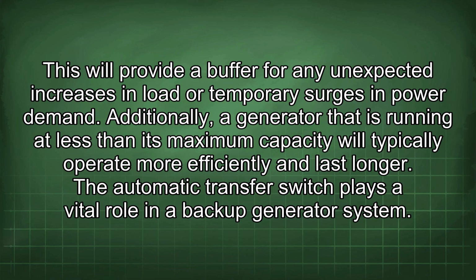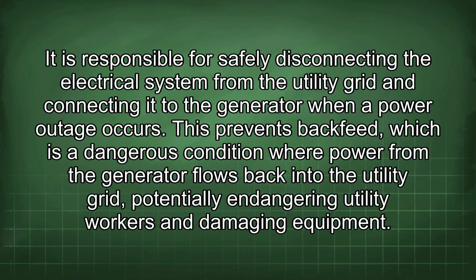The automatic transfer switch plays a vital role in a backup generator system. It is responsible for safely disconnecting the electrical system from the utility grid and connecting it to the generator when a power outage occurs. This prevents backfeed, which is a dangerous condition where power from the generator flows back into the utility grid, potentially endangering utility workers and damaging equipment.